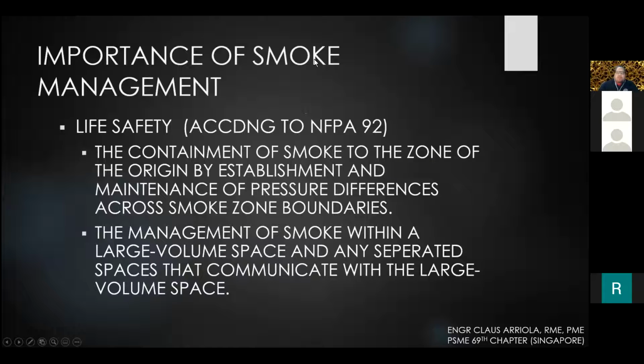So what is the importance of smoke management? Of course, it's about life safety. According to NFPA 92, the containment of smoke to the zone of origin is achieved by establishment and maintenance of pressure differences across smoke boundaries. Why do we need to maintain pressure differences across smoke zone boundaries? If you have a vestibule or safe space, you need it to be at positive pressure relative to the area where the fire or smoke is coming from, so it can push the smoke away from the safe zone or vestibule spaces.